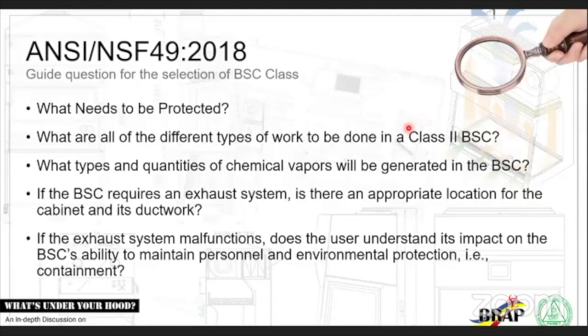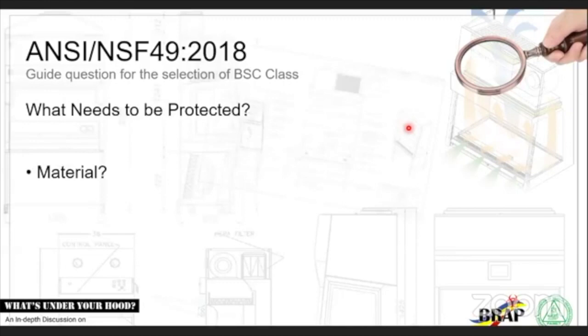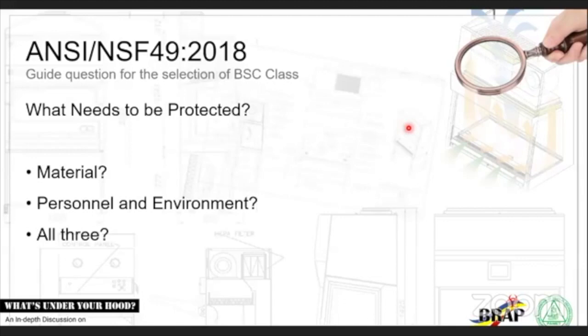Right. So the last question: if the exhaust system malfunctions, does the user understand its impact on the BSC's ability to maintain personnel and environment protection and containment? Now, I think this one is more applicable to your biosafety Class 2 B2s, right? Okay, for now, what needs to be protected? Again, know your material. Know the personnel and the environment. All three, actually. So, do you just want to protect your material or do you want to protect the personnel and environment? So again, firstly, when I show you the differences between the laminar flow hoods and the chemical flow hoods, you need to know what you're handling and what you want to be protected from. Okay? If you want to protect all three, then go for your biosafety cabinets.